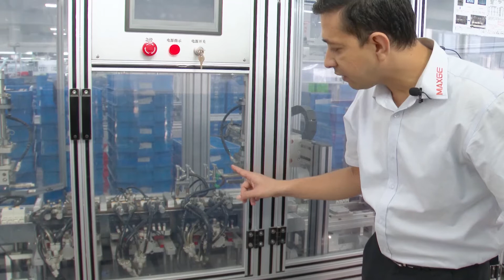So after we do the second calibration, we pass the residual tripping current inside the RCCB, and after that we check by the external tripping with the help of the trip button. Here you can see the process. In the first stage, the residual current is being passed and the RCCB trips, and in the second stage it is tripped externally by the trip button.